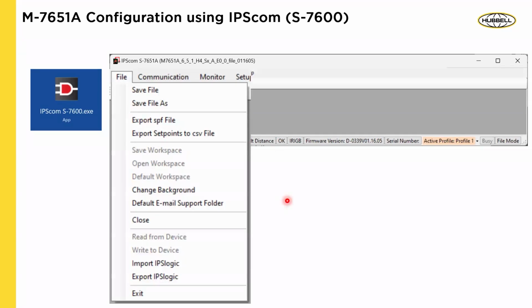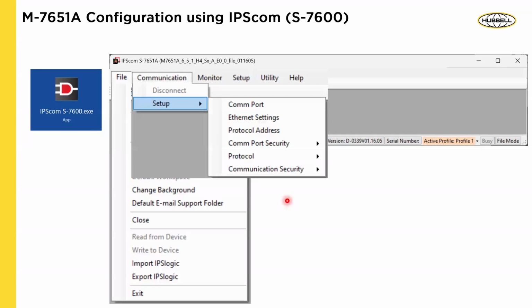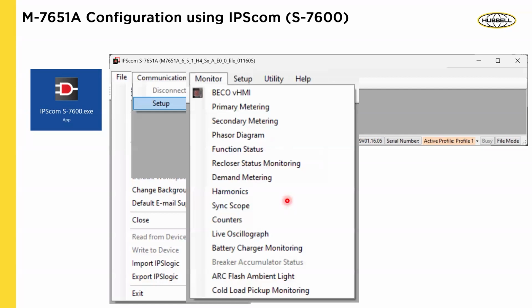Quickly running through, you have file menu options. In communications, you have COM port, Ethernet settings, protocol configuration, security. In monitoring, you could see all of the visual tools we give you to monitor your relay, the live status of each of these things. The list goes on, and we continuously develop more and more, trying to bring more ease of use into the market to show that you don't need a PhD degree to configure a relay. You can be just fine knowing briefly what protection is, how to program it, knowing the syntax, understanding the concepts, and that's good enough for you to go in and start entering the settings.